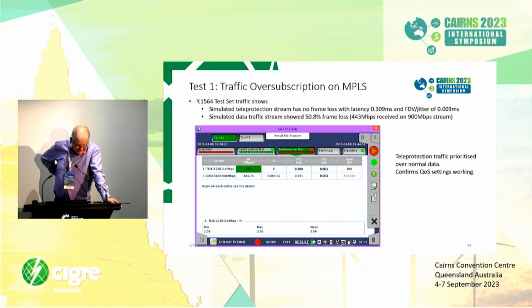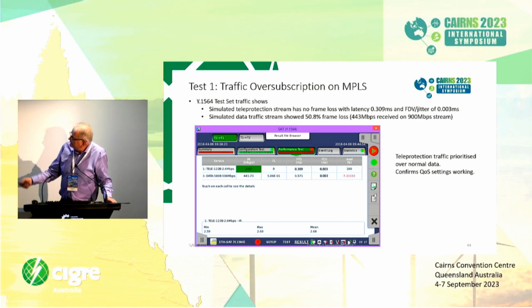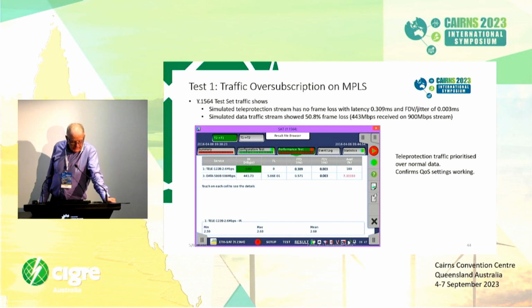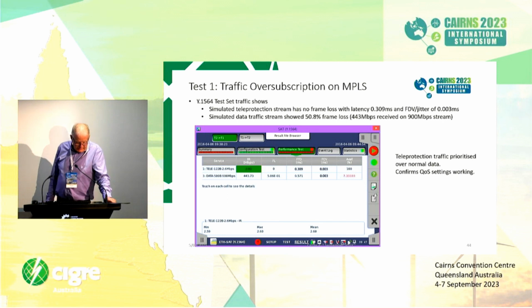So that's the second line, line 3. That's the background data traffic. So it's showing for that, like I say, that 900 megabit per second stream, we're getting 443 megabits received at the far end. Coming back to line 1, that's the simulated teleprotection traffic. We've got a, what is it, a 2.6 megabit per second simulated teleprotection stream, and we're seeing 2.6 megabits received at the remote end with no real FDV, that's the jitter, 3 microseconds, and 100% availability on the teleprotection, which is what we want to see.